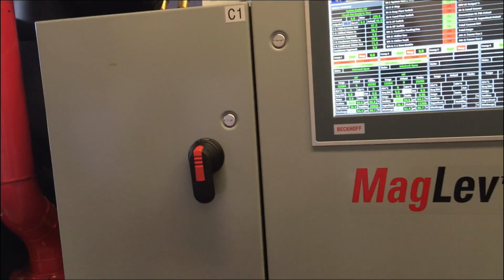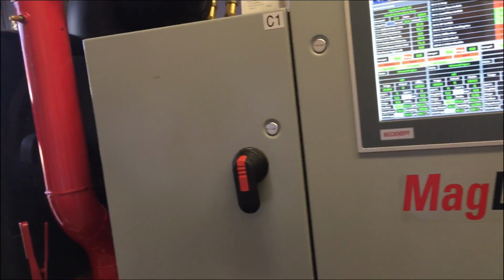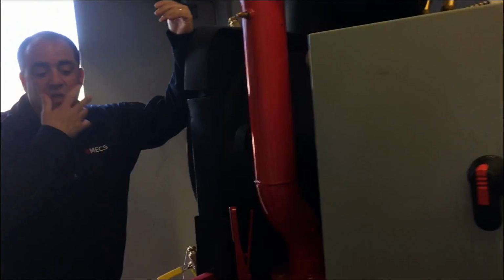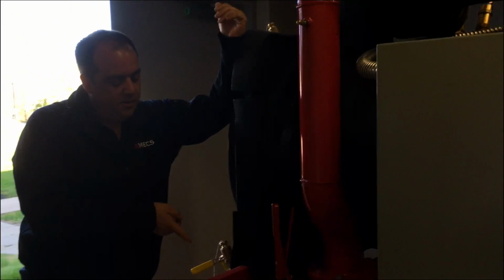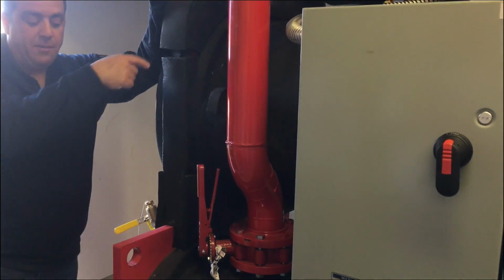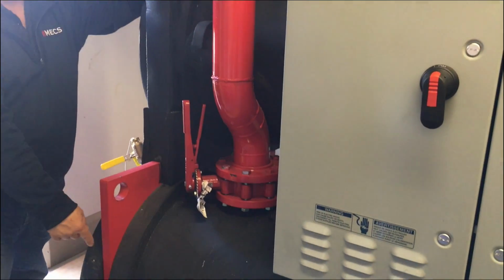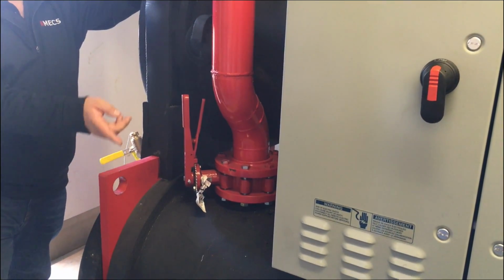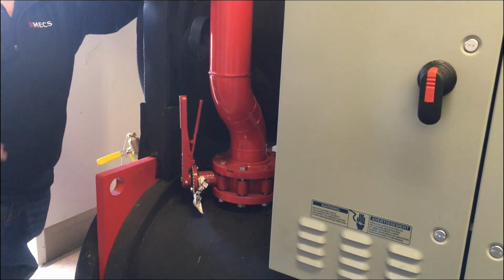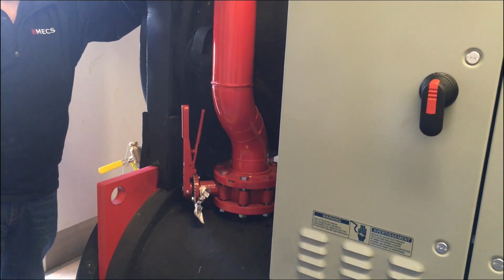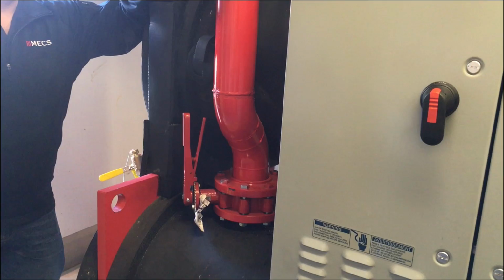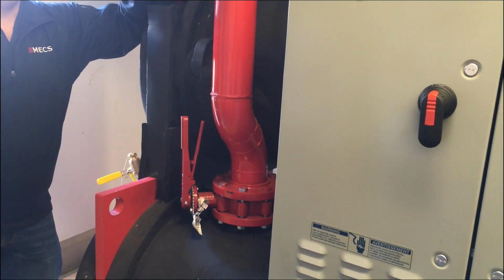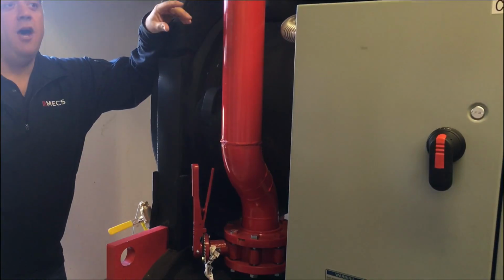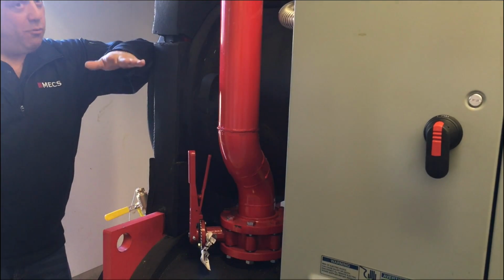And if it gets lower, it's going to close the expansion valves to kind of pump refrigerant back into the condenser. So when the level's up in the condenser, it's going to open the expansion valves to drive more refrigerant back into the evaporator in order to get that level back to the set point. As it drives more refrigerant back into the evaporator, pressure increases because now it's got more refrigerant in it. The compressors are looking at that pressure. So if the pressure increases, the brain of the compressor says we got to run harder to get that pressure back down where it should be.